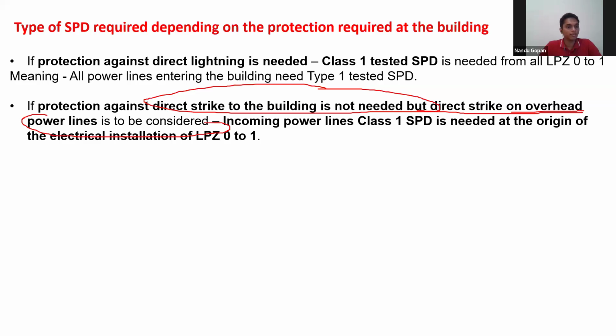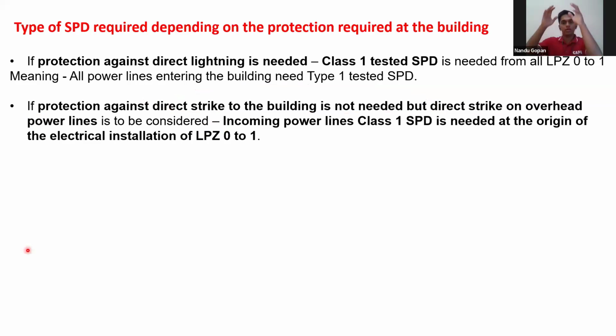SPD. Take a house, for example, which everybody has. Suppose I don't want any protection for the house. If lightning is going to strike the house and I don't care about the damages and don't need protection for it, that is fine. But there will be some power lines coming from outside, from the EB, to your place. For that, you are supposed to consider SPD. So for that power line, when it is coming inside your building, you are supposed to have class 1 SPD. Where the electrical installation starts in your building, you are supposed to have a class 1 SPD. That should be in zone 0 to 1.